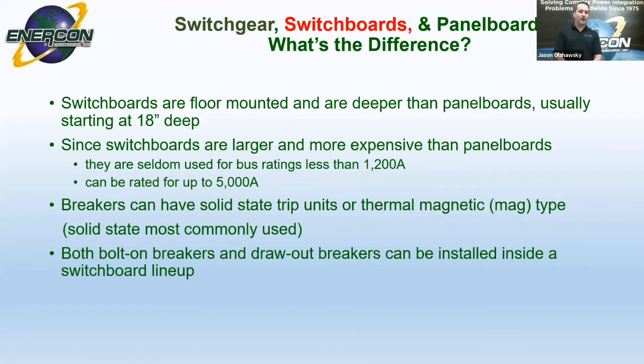Breakers can be equipped with solid state trip units or thermal mag. Solid states are the most commonly used, as they provide you with the ability to have different set points and times for that trip unit, whereas with a thermal mag, it is what you purchase. So if you buy a 50 amp thermal mag trip unit with your breaker, that's what it's going to be, and it's just going to be what you purchased. But you can buy circuit breakers with bolt-on or draw-out type, and bolt-on would be for a place with high vibration or susceptible to vibration, and it'll help keep that breaker firmly installed there in your panel.